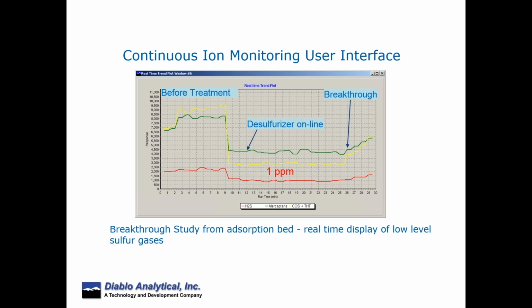You can look at catalysis, you can look at syngas, you can look at essentially any stream that is in the gas phase. We don't want to have any two-phase composition. We want to have only gases, and we achieve that through heat and through appropriate pressure control and sampling system design.